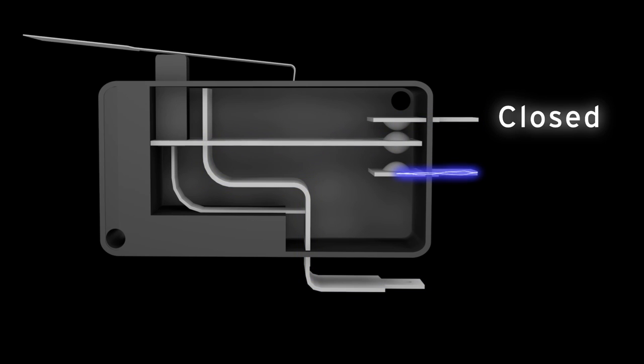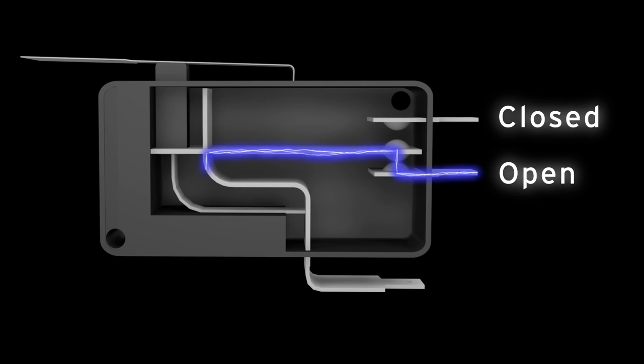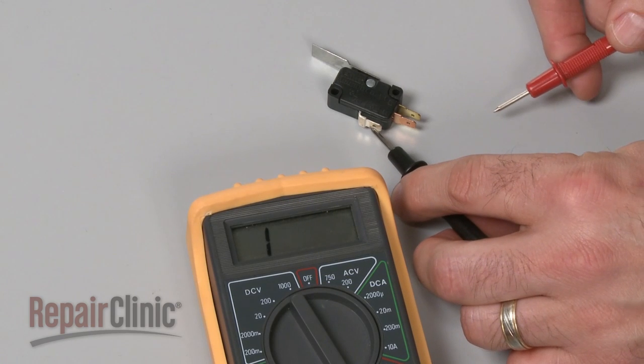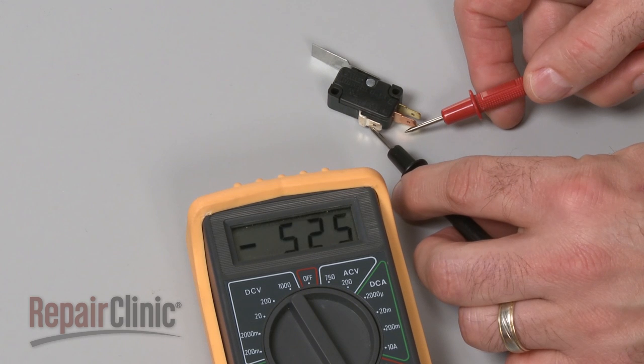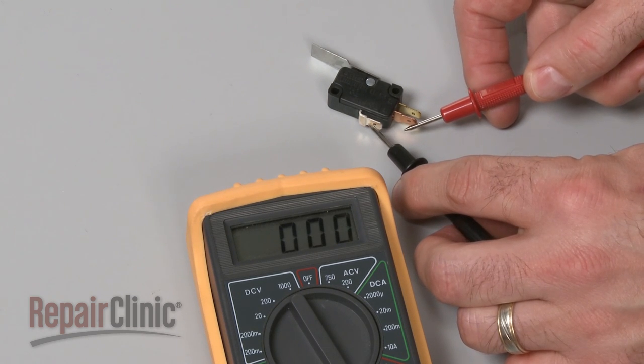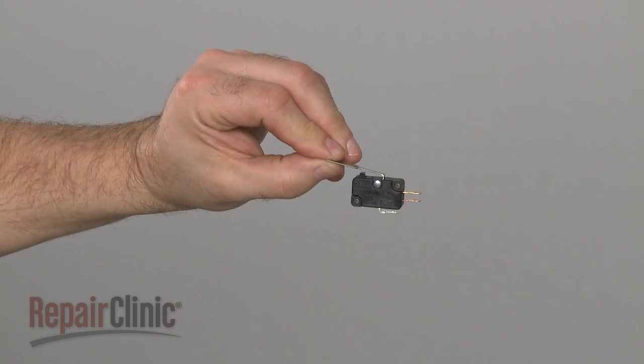Likewise, the normally open terminal should only provide continuity after the switch has been actuated. If a terminal tests positive for continuity when it should not, it's likely that the switch has shorted closed and will need to be replaced.